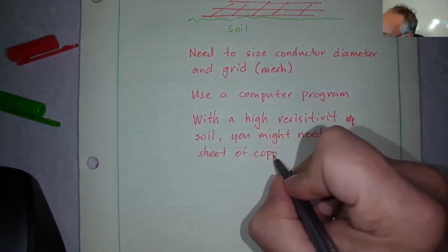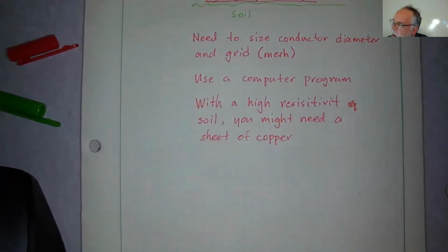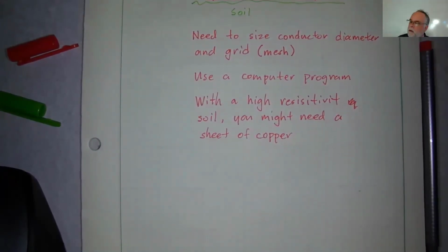On the extreme, if you've got high resistivity, you might have to use a sheet of copper instead of having a ground grid with conductors that are spaced. For example, the chemistry building at Michigan Tech, the ground grid under the chemistry building is a solid sheet of copper, because it's basically built on rock.